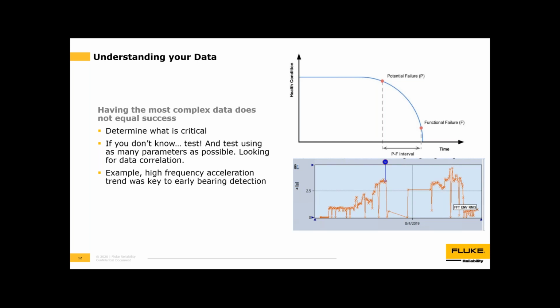In some cases, if you're brand new to collecting data on this machine, it's important to look at what type of data you can collect with your sensor, and try to take as many different parameters as possible. If you can take overall data in both velocity and acceleration, or access to shock pulse or envelope readings, you should collect this so you can correlate it and look for patterns.